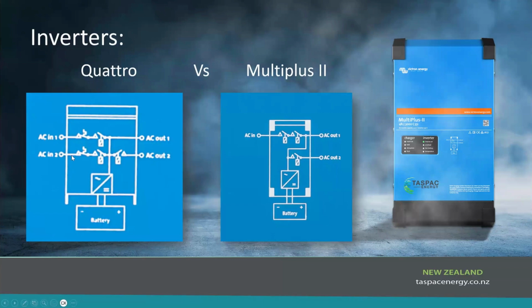And that's the same with the Quattro inverters. So if you're connected to the grid, say, you could run your big loads such as your spa pool, your water heating maybe, whatever bigger loads that you don't really need running, they're kind of nice to haves, optionals, but you want them to drop out when the grid drops out, you can just wire those in on a second phase, if you like, going to the switchboard. It'll be literally the same phase, but a second mains cable going into your switchboard, running those loads, and they will drop out when the grid drops out.